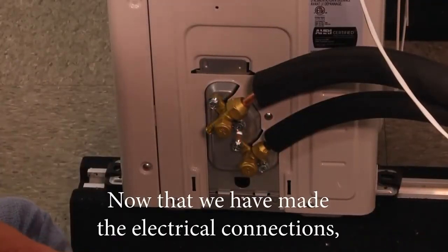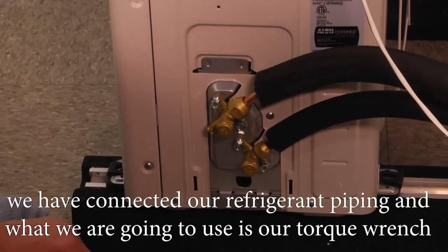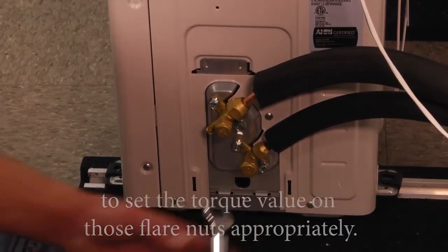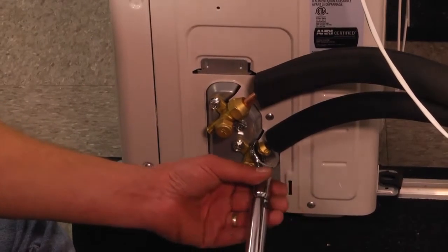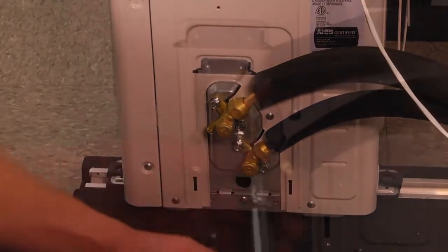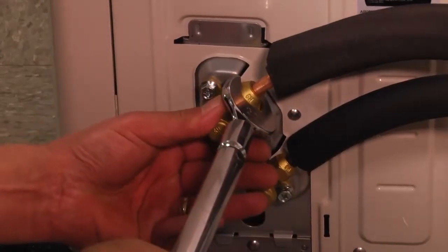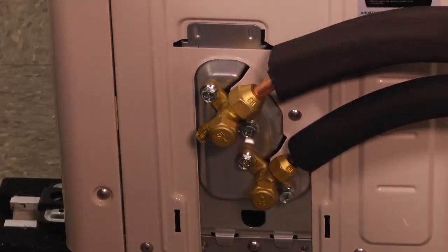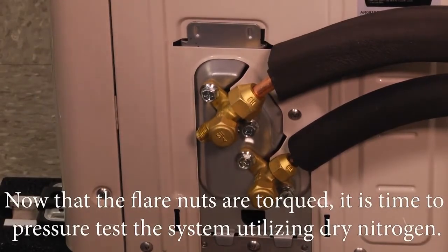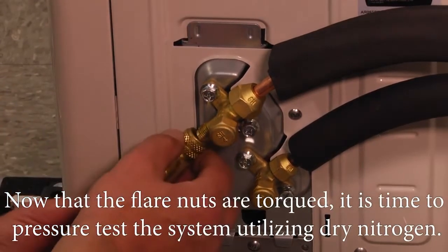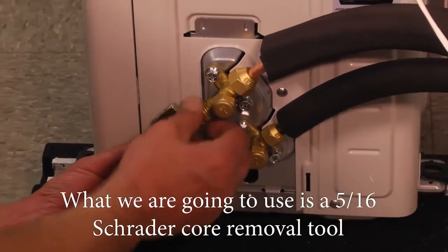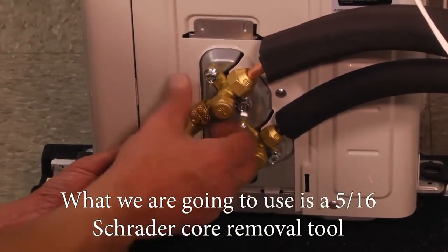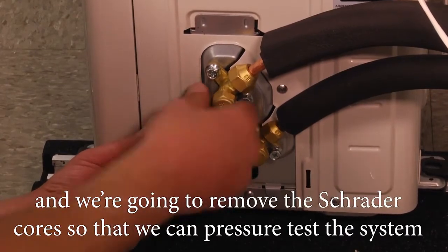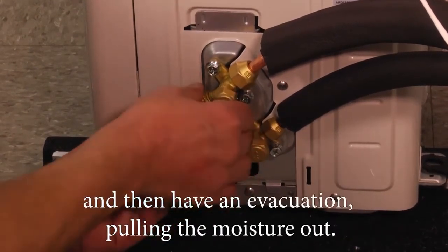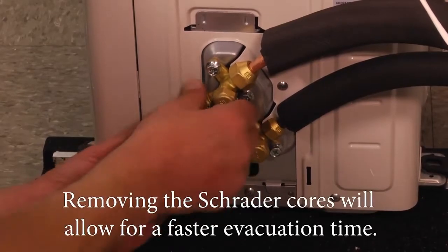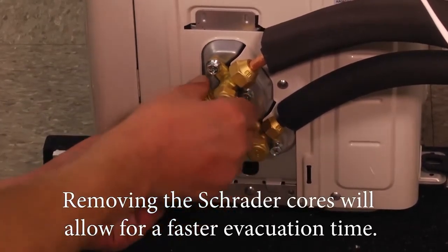So now that we've made the electrical connections, we've connected our refrigerant piping, and what we're going to use is our torque wrench to set the torque value on those flare nuts appropriately. Now that the flare nuts are torqued, it's time to pressure test the system utilizing dry nitrogen. What we're going to use is a 5/16 Schrader core removal tool, and we're going to remove the Schrader cores so that we can pressure test the system and then have an evacuation, pulling the moisture out. Removing the Schrader cores will allow for a faster evacuation time.